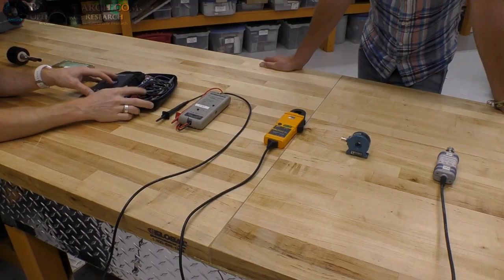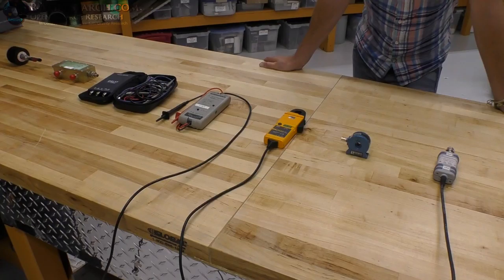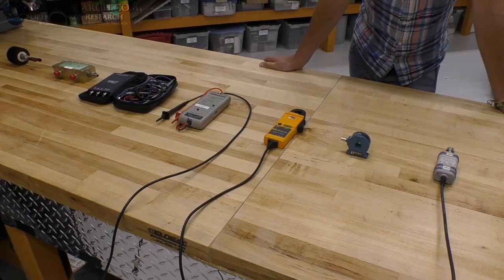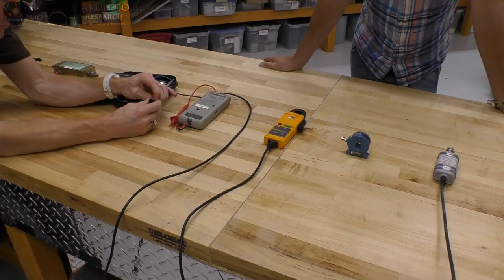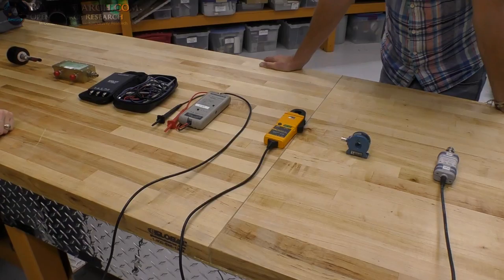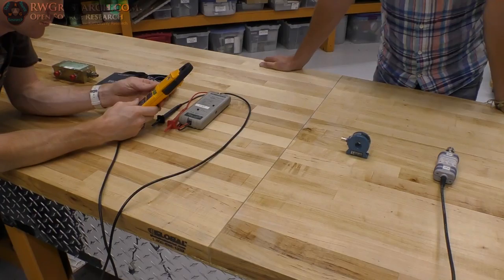The first mistake that I found, as Russ has alluded to, is using the current meters, RMS meters for example, to do AC measurements with voltage and current. Fine for DC measurements, no problem. Pretty good for low frequency, sort of 50 hertz, maybe a little bit above. But they don't consider any power factor between the voltage and current, so you're not actually sure how much power you've actually got. When you step into AC, and particularly as you go higher in frequency, you need increasing amounts of specialist equipment.